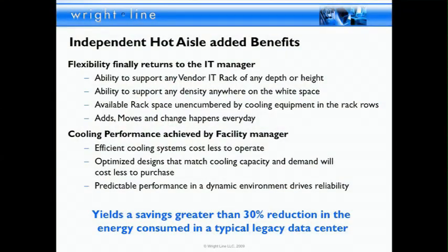And then remember, everything we talked about is rack integrated. Here's a concept for the independent hot aisle. Brings a lot of different benefits. Ideally, the flexibility. Remember, I talked about the rack capability. Well, you can actually, with this type of system, support any type rack you want, any height, any width, any depth, as long as you're readjusting to the hot aisle and maintain total containment.